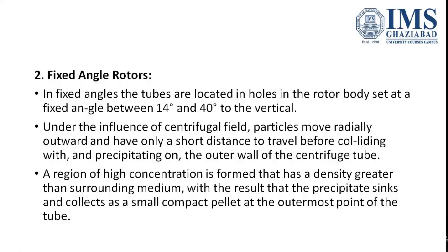Now, the fixed angle rotors, this is the most common type of centrifuge rotor that is found in labs, in which the angle in which we place the tubes is fixed. It can be 14 degree to 40 degree. And under the influence of centrifugal field, the particles move radially outward because the centrifugal force is applied radially outward.